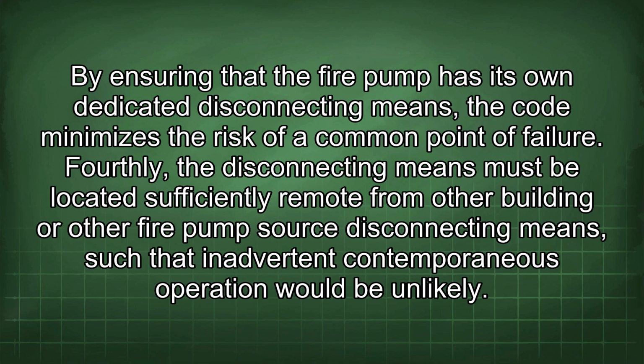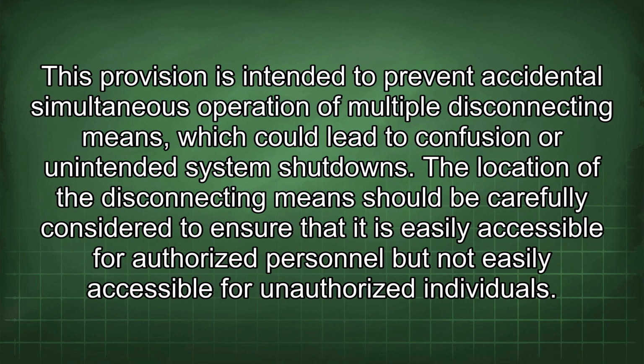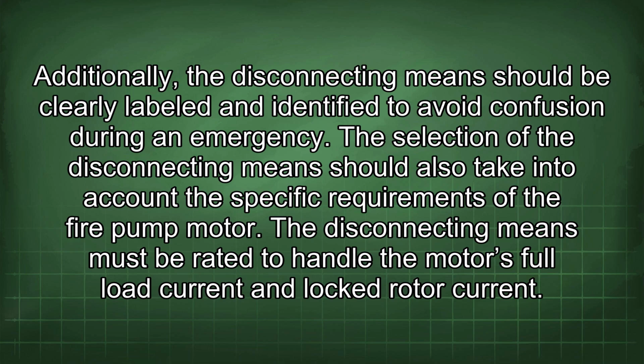Fourthly, the disconnecting means must be located sufficiently remote from other building or other fire pump source disconnecting means such that an inadvertent contemporaneous operation would be unlikely. This provision is intended to prevent accidental simultaneous operation of multiple disconnecting means, which could lead to confusion or unintended system shutdowns. The location of the disconnecting means should be carefully considered to ensure that it is easily accessible for authorized personnel, but not easily accessible for unauthorized individuals. Additionally, the disconnecting means should be clearly labeled and identified to avoid confusion during an emergency.